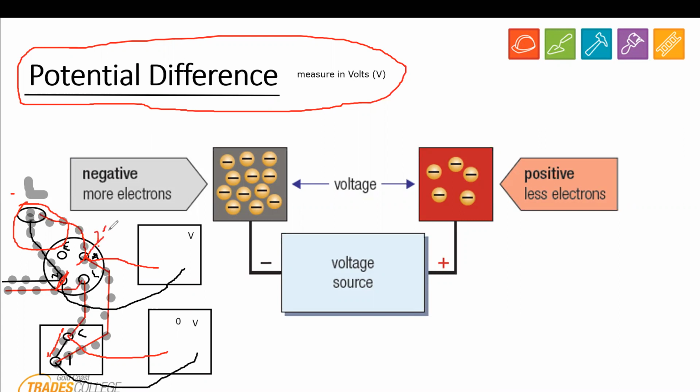Going in, you're going to have your 230. And this is going to use all of that. And then at the bottom here, you're going to have nothing. 230 take away 0 is then where our correct term is how we measured it. It's there. All right. Extremely important to understand that when we're measuring voltage, we're measuring the difference from one side to the other. All right, you can measure a live part of a circuit. Excuse me. You can still try and measure voltage on a circuit which you can see is switched on, and you can get 0. All right.